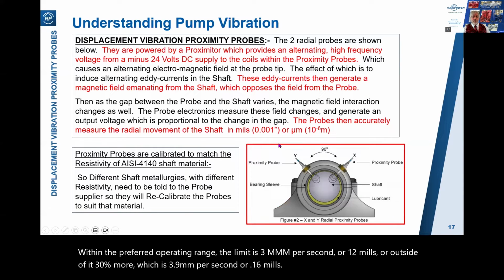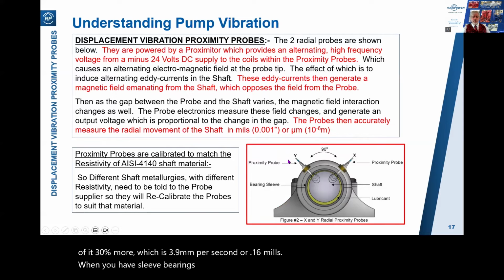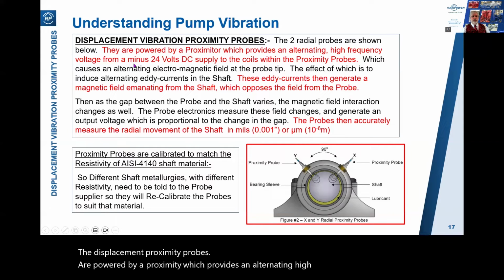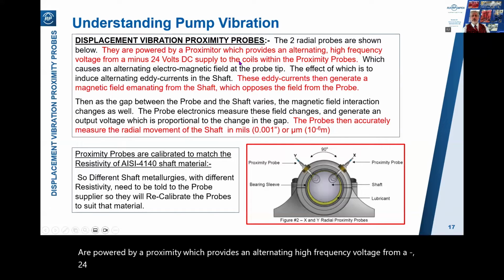When you have sleeve bearings, then you use displacement proximity probes. These measure the gap between the shaft and the bearing sleeve. More specifically, and a little more verbose, the displacement proximity probes are powered by a proximeter, which provides an alternating high-frequency voltage from a minus 24-volt DC supply to the coils within the proximity probes.